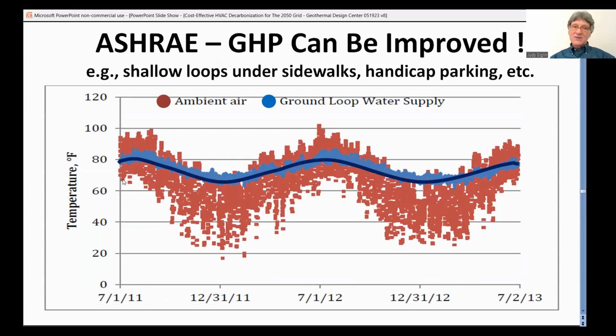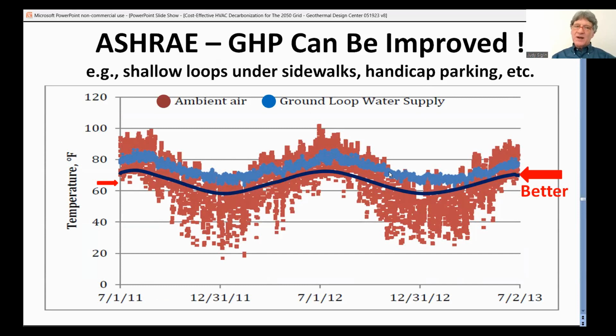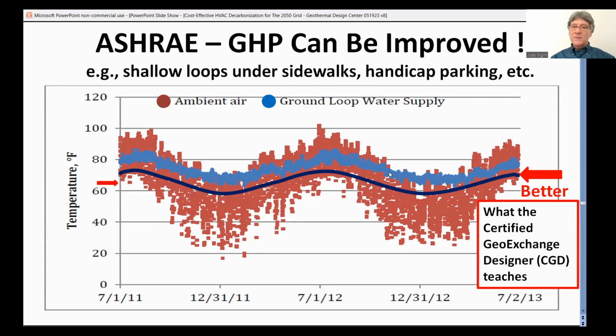Now I happen to know this, so this is the curve of the ground loop in blue, and the red is the air temperatures. You can see it's got an annual cycle. Now I happen to know that the average air temperature in Atlanta is more like 54 degrees, so that loop is running a little hot. It should be running down here — that would be better, that would produce a more efficient solution. So this wasn't quite engineered to the perfect stage of what we do now in this field.